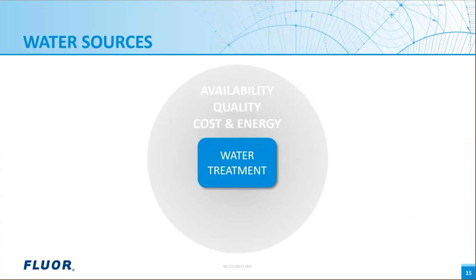Screening of the available water sources at the site should start early. Things to consider for the screening process are availability. Is there sufficient availability to satisfy demand during all seasons, potential periods of drought, projected future demand? And then there's quality. What is the water quality and how stable is it? Does it change seasonally? We are most interested in suspended solids, dissolved solids, silica, chloride, and organic matter, since these can lead to fouling, scaling, and corrosion. Cost and energy. Having a good basis for availability and quality allows you to design a system that optimizes cost and energy while achieving the project goals.